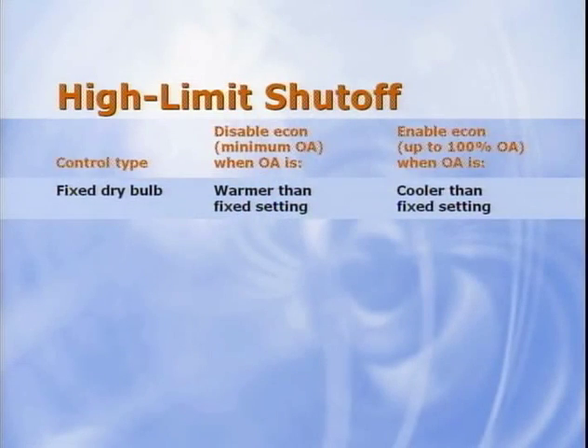The selection of the economizer control strategy and shutoff setting have an impact on energy use. Our May broadcast discussed several economizer control strategies, but I'll just review 3 of them that are probably the most common to rooftop VAV systems. Fixed dry bulb control compares the dry bulb temperature of the outdoor air to a predetermined high limit shutoff setting and disables the economizer whenever the outdoor dry bulb is above this limit. This method is simple and relatively inexpensive. But if the shutoff setting is too high, this control strategy can bring in cool but humid outdoor air, which may actually increase mechanical cooling energy.